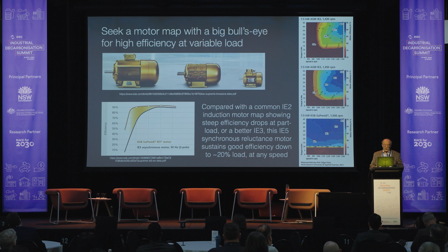And this is relevant if you have the same problem we do in the US, I suspect you may, namely that half of our industrial motors never exceed 60% of their rated load and a third never exceeds 50% of their rated load. So they're a lot less efficient than the full load nameplate rating says. And also, when you underload an asynchronous motor, it runs faster, so it wastes more energy in pumps and fans, which are cube law machines, by driving more flow than you need. Well, because of those two effects of pervasive oversizing, right-sized new motors will save more energy than expected, and they'll cost less because although price does not correlate with efficiency, it correlates very well with size.